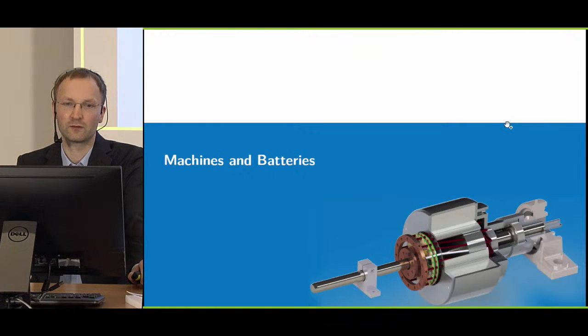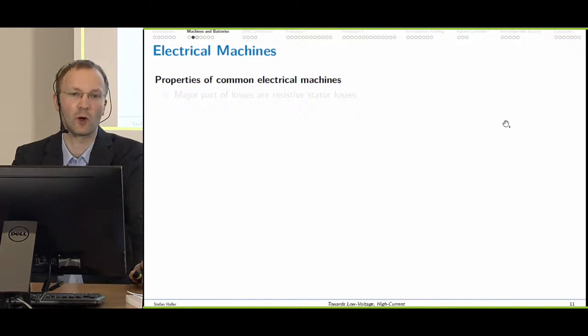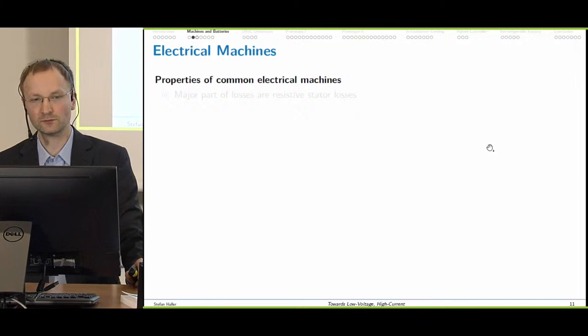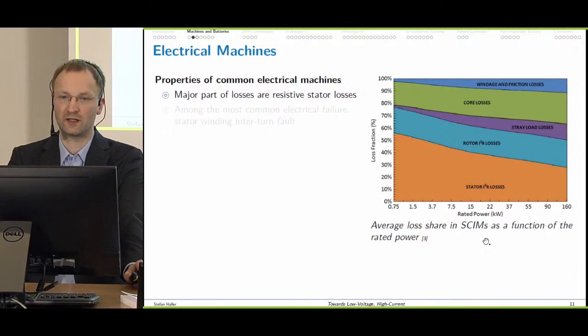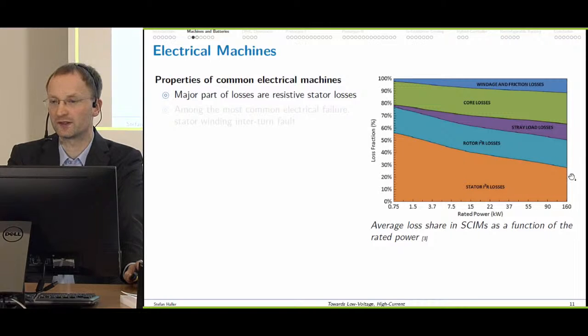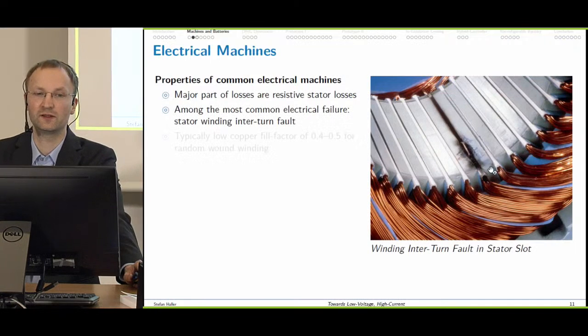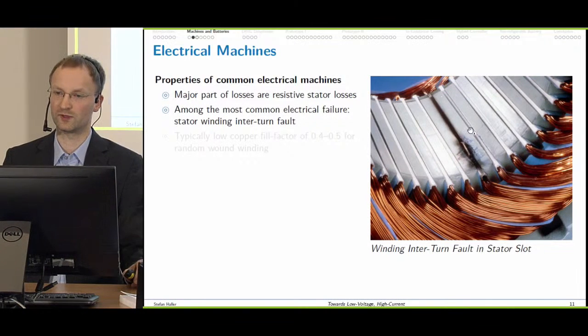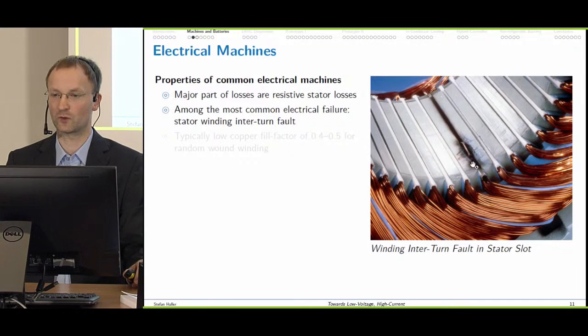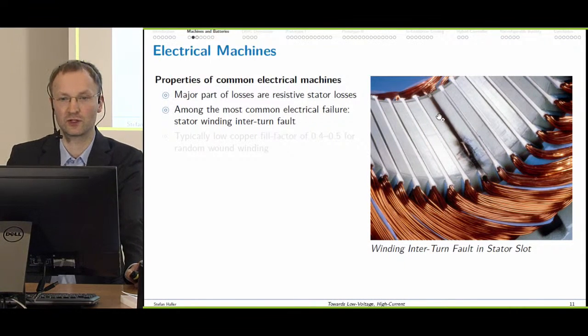Let's have a look at machines and batteries, specifically some common properties of electrical machines. The major part of the losses of an electrical machine are resistive stator losses. What we see here is an example of a squirrel cage industrial induction machine. And even at 160 kilowatt, the resistive losses are the largest single loss share in the machine. Among the most common electrical failures is the stator winding inter-turn fault. That's what we see here in the picture. It might start as a short between 2 adjacent wires or a short to the stator slot, and finally propagates in the coil and ultimately destroys the electrical machine.